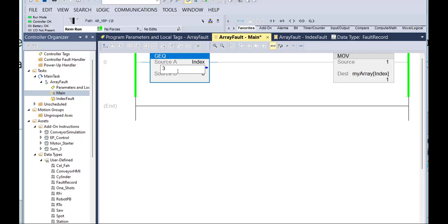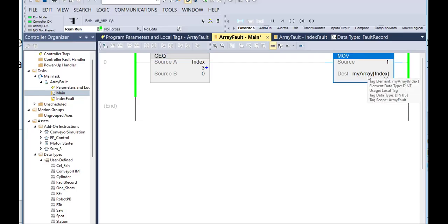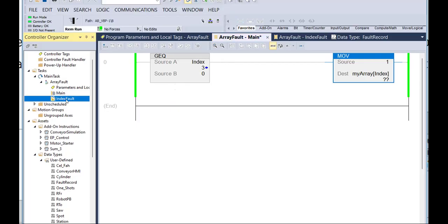So let's look at if this will cause the shutdown again. It didn't, right? Notice here it has unknown, the question mark. That means it didn't execute this instruction because the PLC controller ran into a problem, the fault, and that fault will automatically call this subroutine because you already set it up as the fault handler, right?